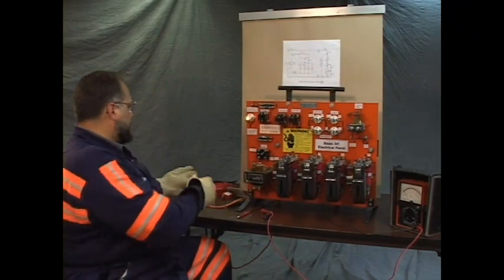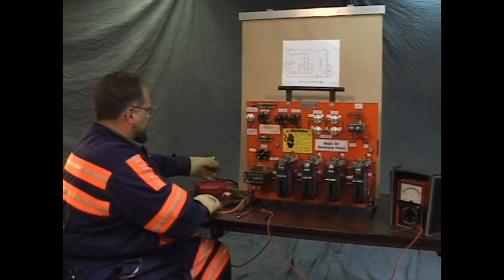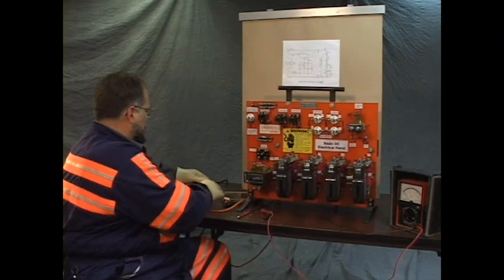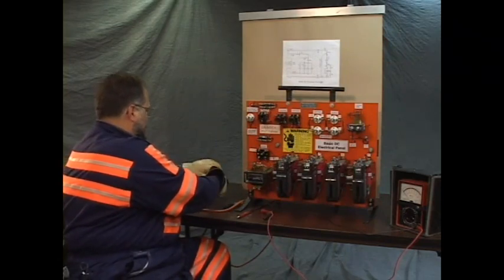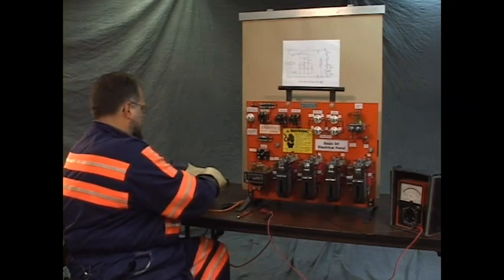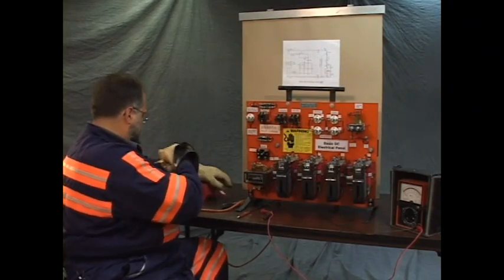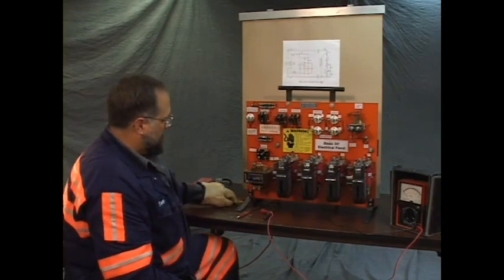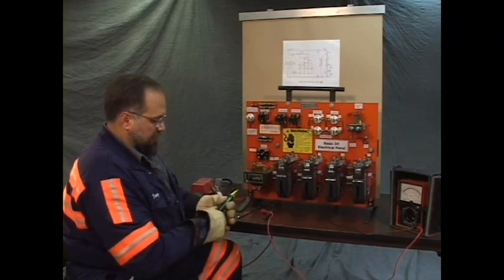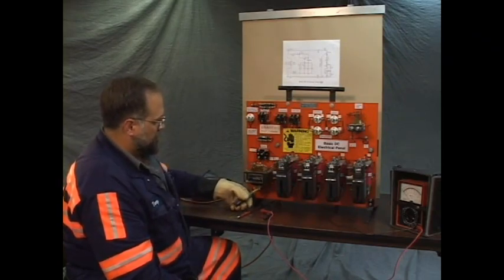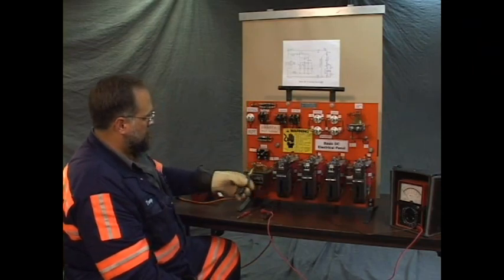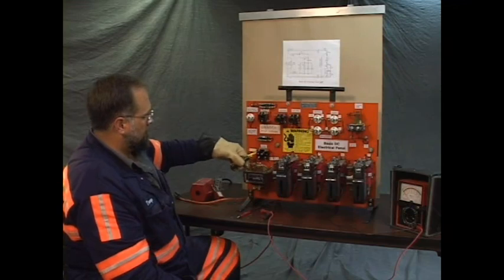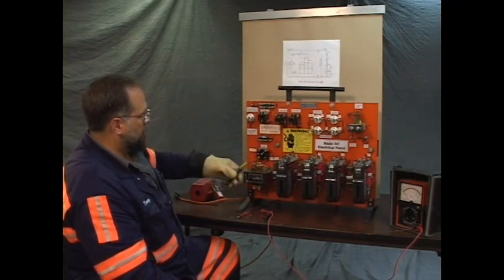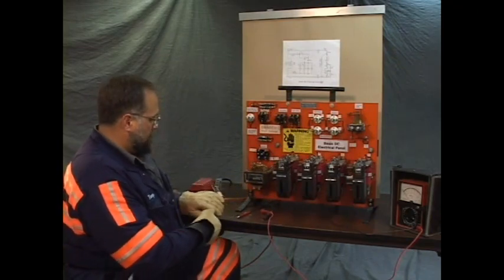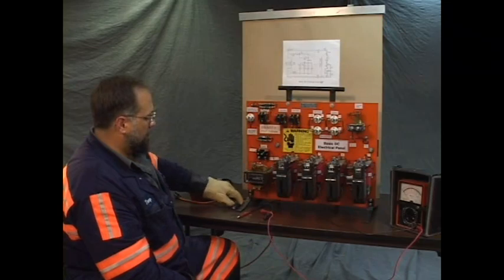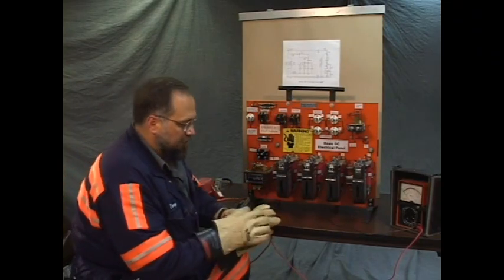Okay, let's make the panel safe by disconnecting the power. We're going to lock and tag. Put the key in your pocket. Now, although we've disconnected it, we're still going to test this with a voltage tester. You'll get the occasional chirp from moving the tester too quickly. That's not indicative of power on a circuit. When you have power, it chirps non-stop. After we've determined the power is off, we can take the gloves away.